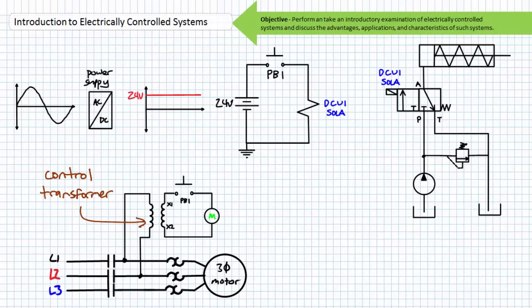For AC systems incorporating motors, the level of control voltage necessary to operate an electrically controlled system ordinarily comes from a control transformer. This device steps down high voltage primary input to a safe and more usable pilot value. In the case of an electrically controlled system employing three-phase AC, you can actually use the line-to-line voltage between two of the phases as the input to the primary coil. Let's say an electrically controlled system using 480 volt three-phase AC as primary input requires 120 volts single-phase AC as a pilot signal. The primary input to the control transformer would be the 480 volt single-phase AC between any two of the three phases, and a 4-to-1 step-down transformer would step this down to 120 volt single-phase AC.